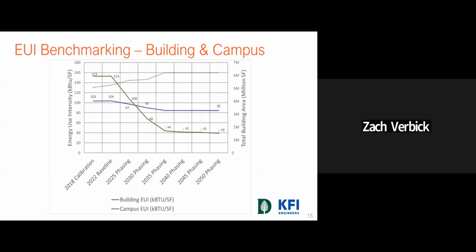So as we look at a comparison, this chart compares building level EUI, which is just heat energy going into the building, with campus level EUI. You can see the difference. With a conventional system, which is currently what Dartmouth has, it hurts the campus level EUI because of those inefficiencies, and the building isn't penalized for it given how the system boundaries are drawn. Then the equation flips as equipment is changed out on the plant side. Overall, this shows nearly a 75% reduction in campus energy use, which is a significant impact to the campus overall.